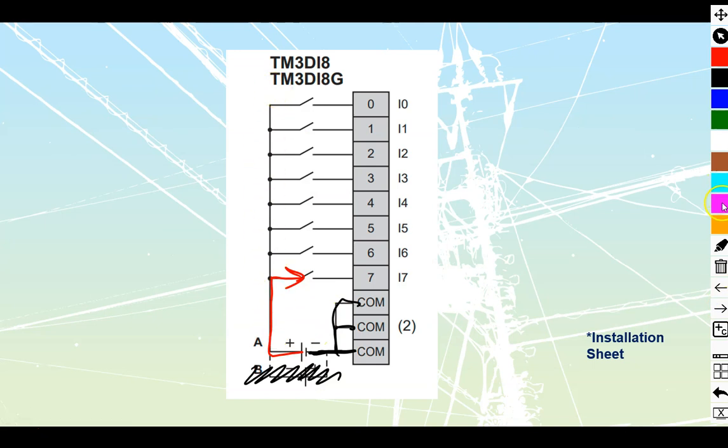One thing that is missing on here that actually surprised me - because Schneider has been very good about putting these onto pretty much every other data sheet they have, but for some reason this family, they forgot to add in the fusing that you are going to have over here on your 24 volt power supply. So we'll add that in ourselves. Manufacturers are no different than you or I. They make mistakes as well and stuff sometimes doesn't always get caught. So we'll add that fusing in ourselves.